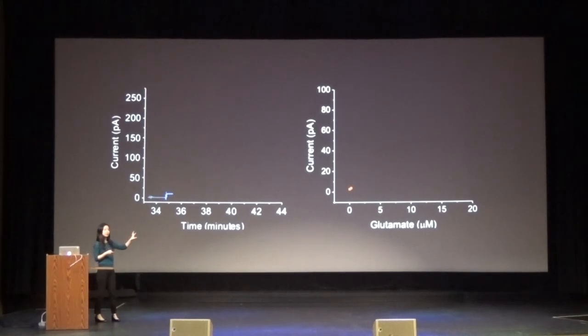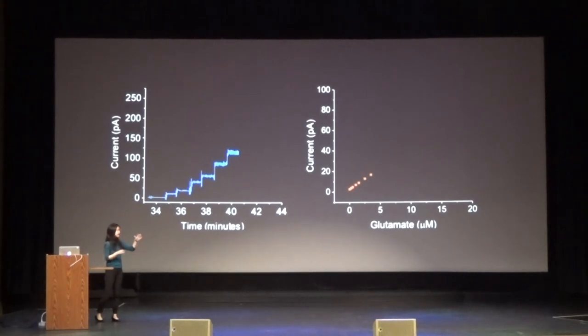I can translate that to my calibration curve on the right-hand side, where I look at how the current level changes as I increase the concentration of glutamate, with current measured on the y-axis. As I do a few more injections to build up the calibration curve, you can see more orange dots appearing, and a slope starting to emerge.